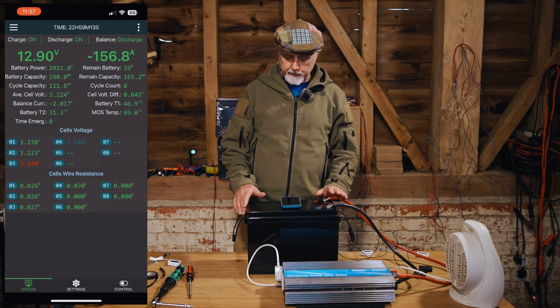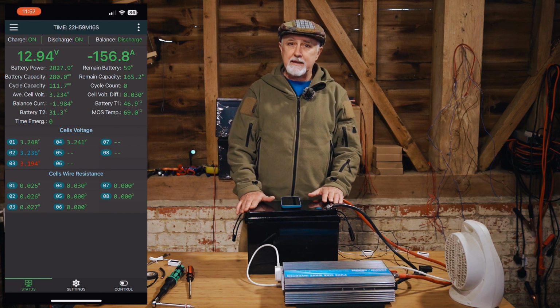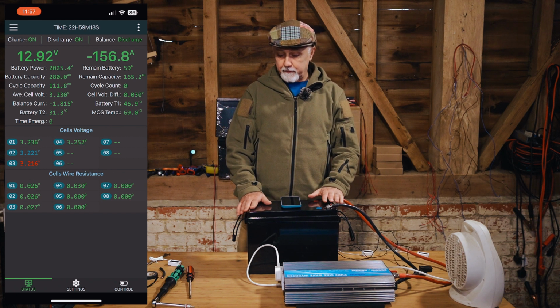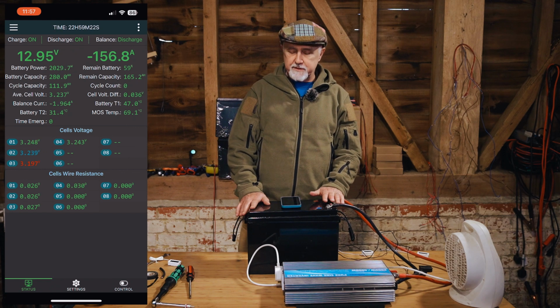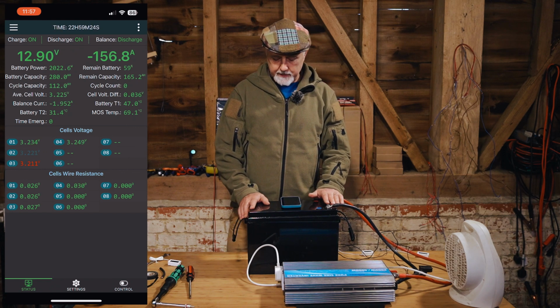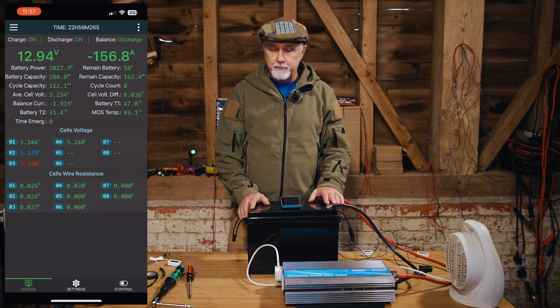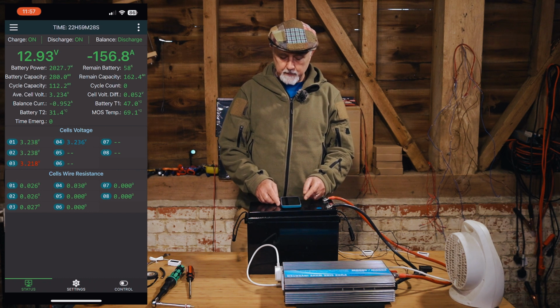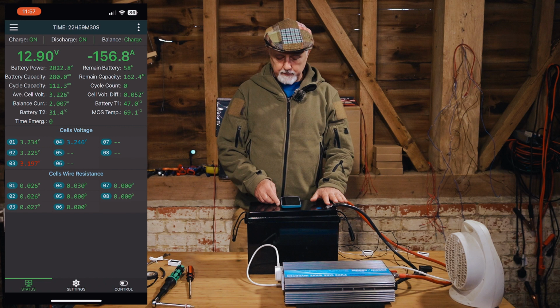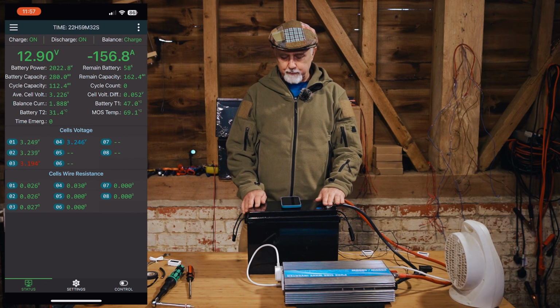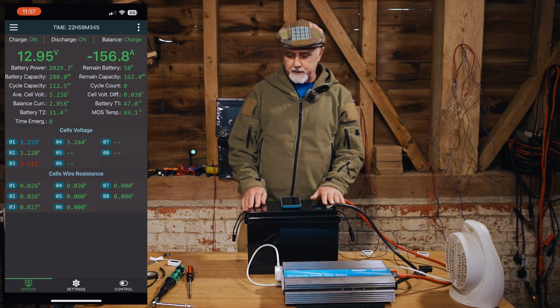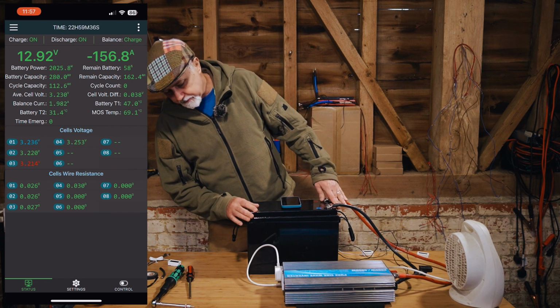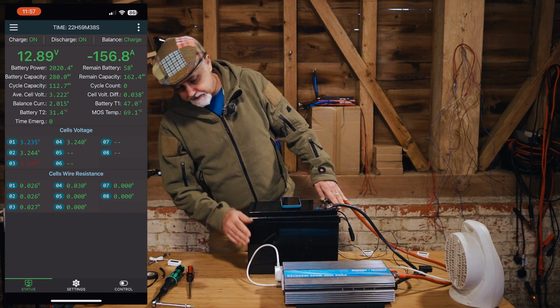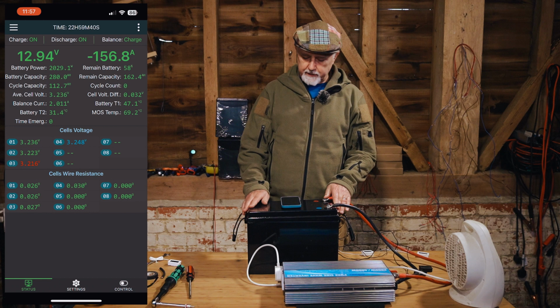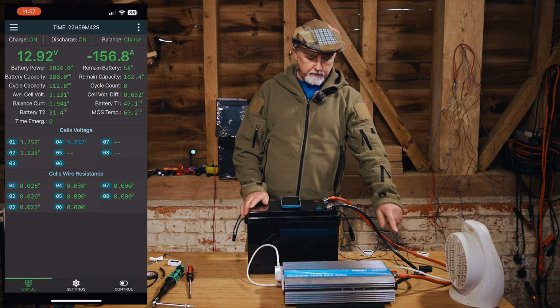Right, so we've been running for 45 minutes. For the last 20 minutes at least, we've been running constantly at 156 point something amps - at the moment it's 156.8 amps. The battery, the BMS, is still reporting 12.95, 12.90. The inverter is reporting 11.9, so we drop 1 volt going down the cables. That's quite normal.